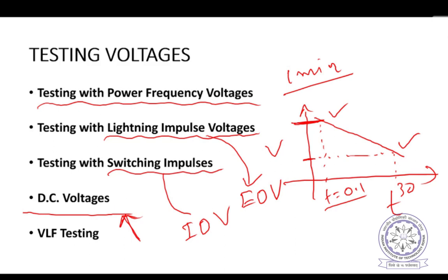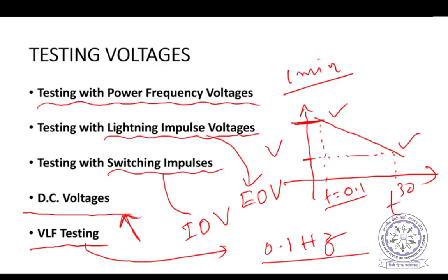But there were some apprehensions that testing under DC is not adequate. So after that, people came up with very low frequency testing. Instead of completely DC, a small frequency of 0.1 Hz AC. It corresponds to AC also, but at the same time it decreases the reactive power requirement because the frequency is very small. Therefore, VLF testing, or very low frequency testing, has come into the picture. So these are the various testing voltages that are used for testing power equipment.